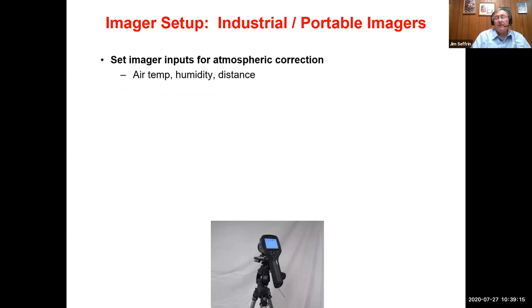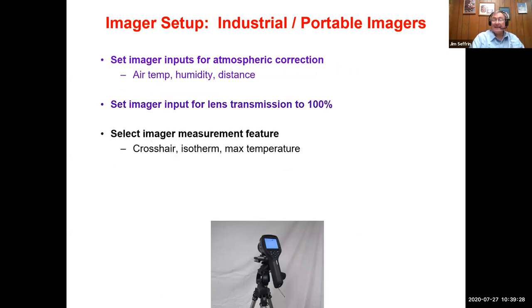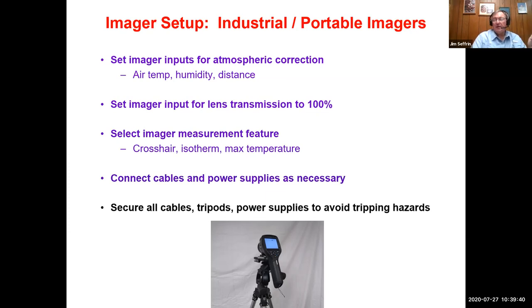When you set up your industrial grade or portable imager, you're going to set your imager inputs for atmospheric correction, such as air temperature, humidity, and distance. You'll set your imager input for lens transmission to 100%. You then select an appropriate imager measurement feature, such as crosshair, isotherm, or if you're so equipped, max temperature. You connect your cables and power supplies as necessary, and secure all cables, tripods, and power supplies to avoid tripping hazards in the screening area.